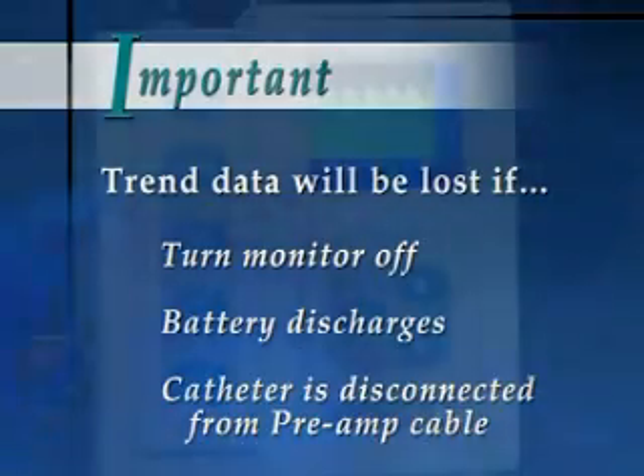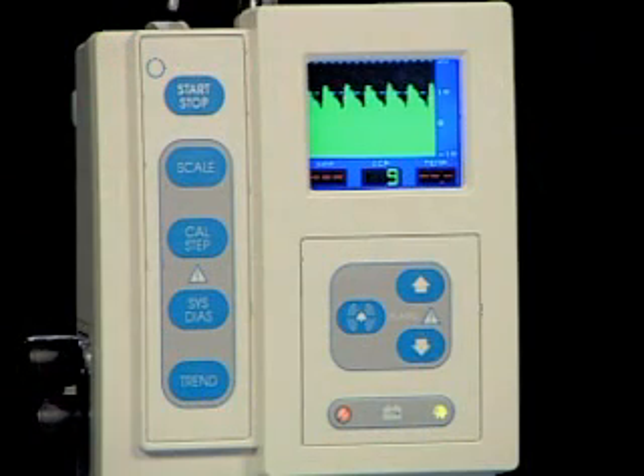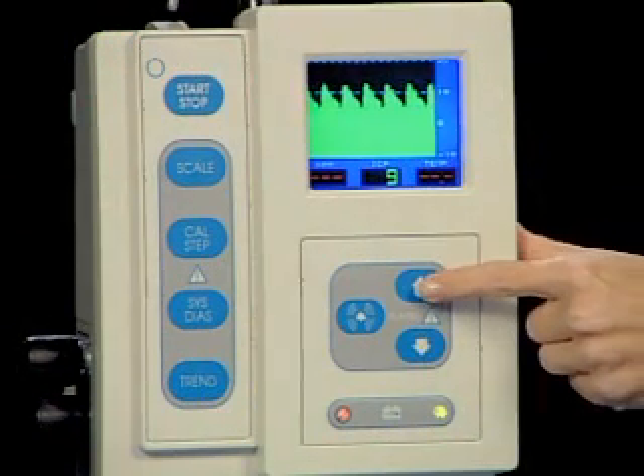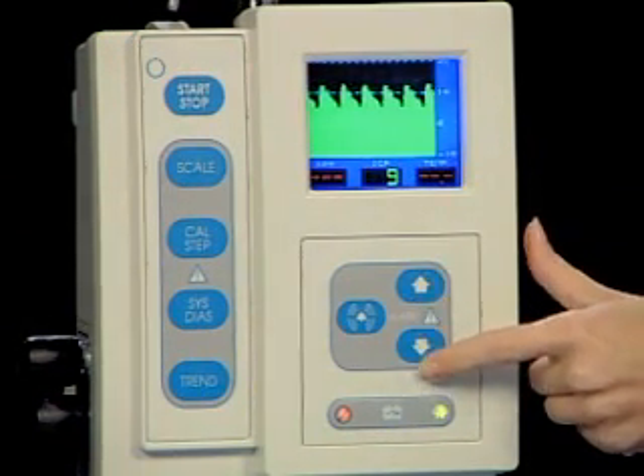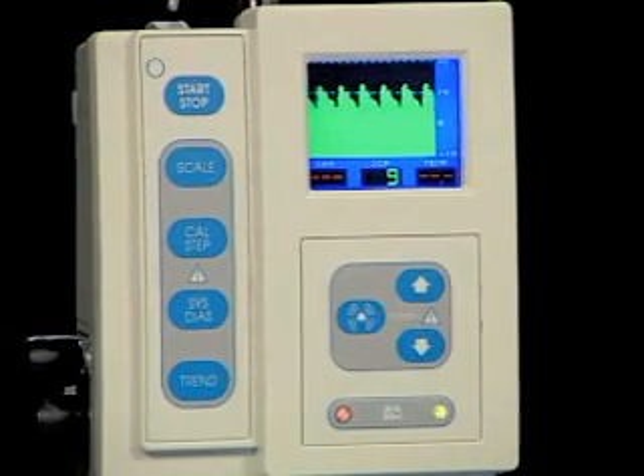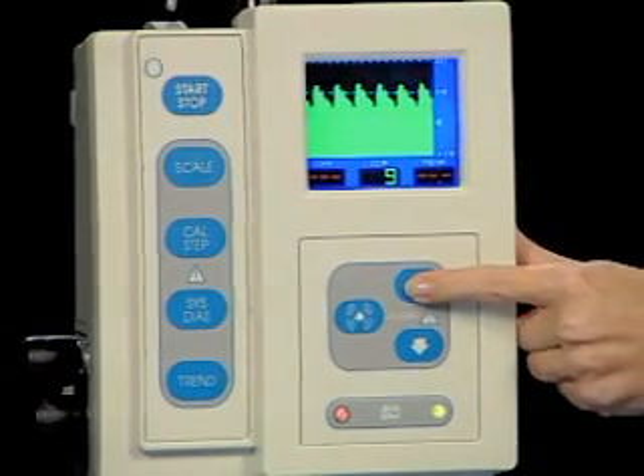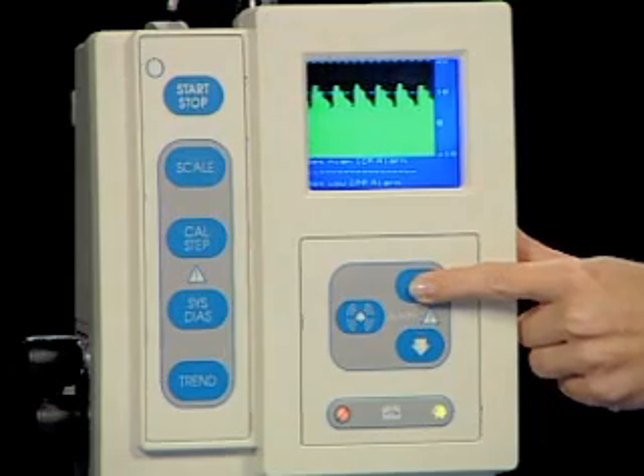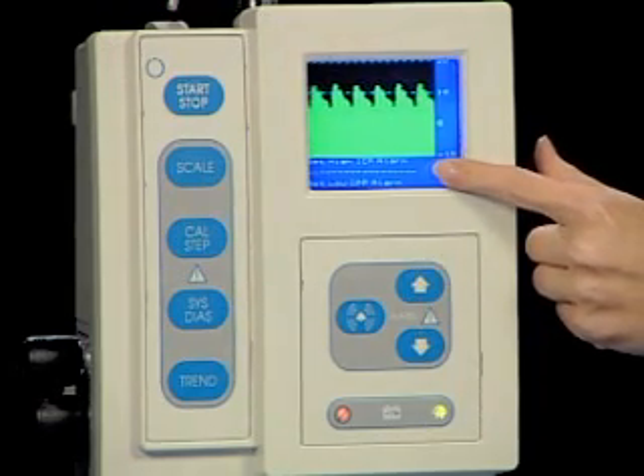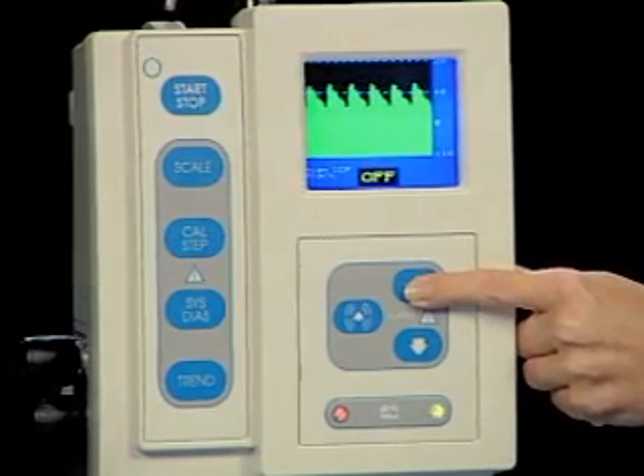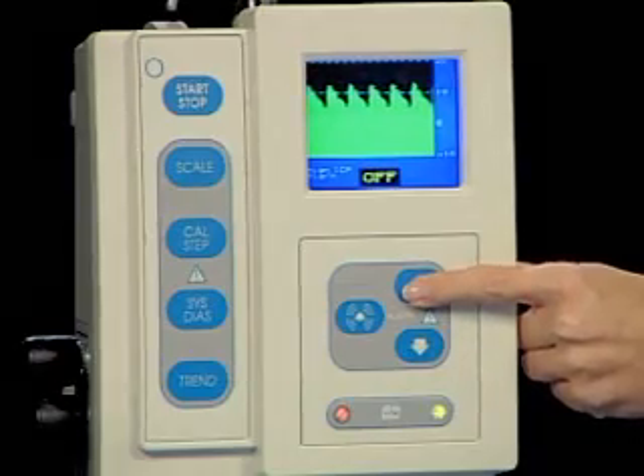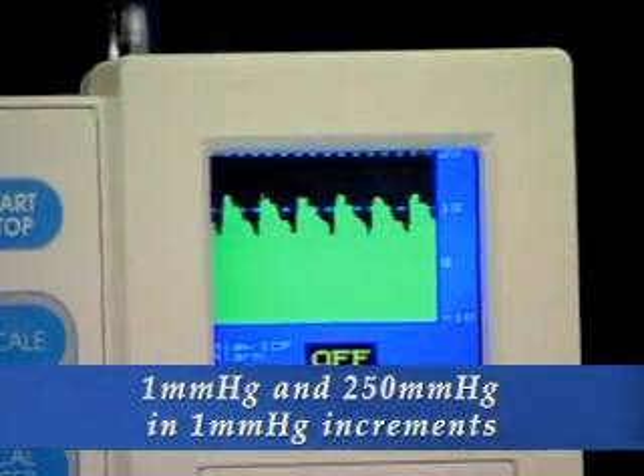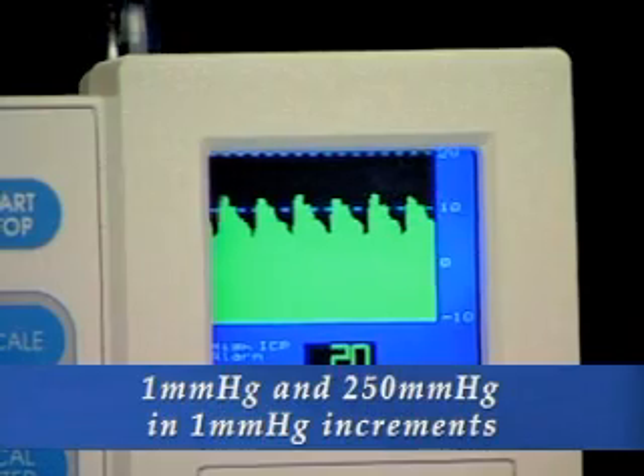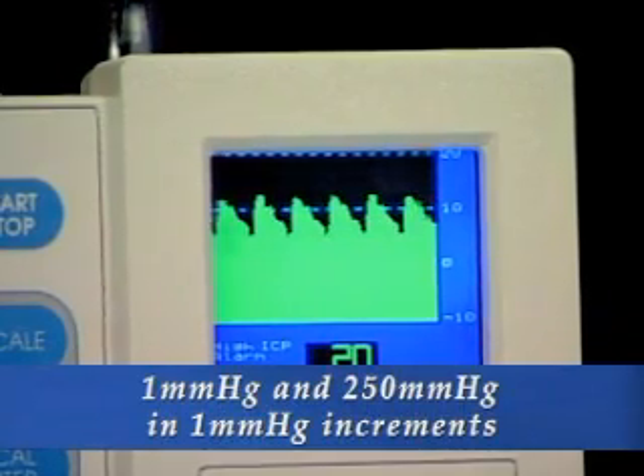The MPM-1 is equipped with a high ICP and a low CPP alarm. To access the alarm, press either the up or down button to view the Alarm Select screen. Press the up button to select the high ICP alarm. Use the arrows to scroll to set the desired value. The alarm value may be adjusted between 1 millimeter of mercury and 250 millimeters of mercury in 1 millimeter of mercury increments.